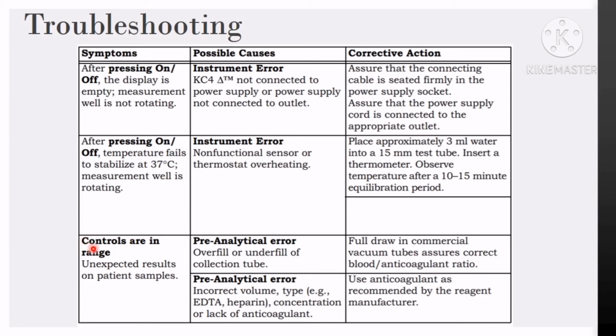Number 3, the last one, is controls are in range but unexpected results on patient samples. Now, with a lot of samples we can expect some sort of result, but if it's far from what we expected, then we can probably blame it on the device. So there are two causes. It's a pre-analytical error, whether it's overfill or underfill of the collection tube, or incorrect values, such as the type of EDTA or heparin, and the concentration or lack of anticoagulant. What you can do is a full draw in commercial vacuum tubes, which assures the correct blood to anticoagulant ratio, or use anticoagulant as recommended by the reagent manufacturer.